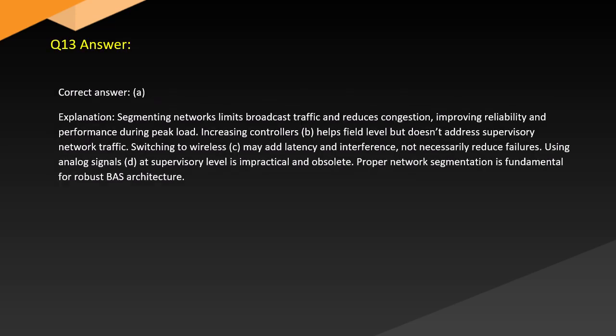Answer. Correct answer: A. Explanation. Segmenting networks limits broadcast traffic and reduces congestion, improving reliability and performance during peak load. Increasing controllers, B, helps at the field level but doesn't address supervisory network traffic. Switching to wireless, C, may add latency and interference, not necessarily reduce failures. Using analog signals, D, at the supervisory level is impractical and obsolete. Proper network segmentation is fundamental for robust BAS architecture.